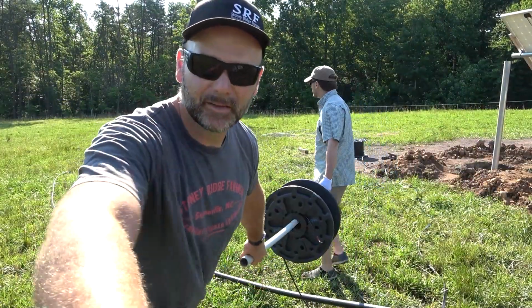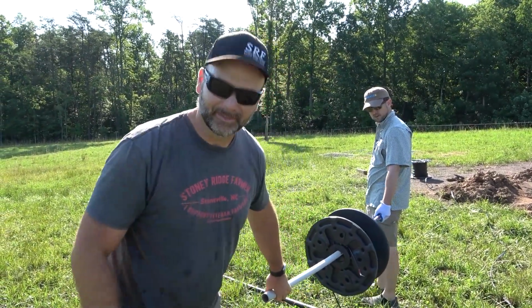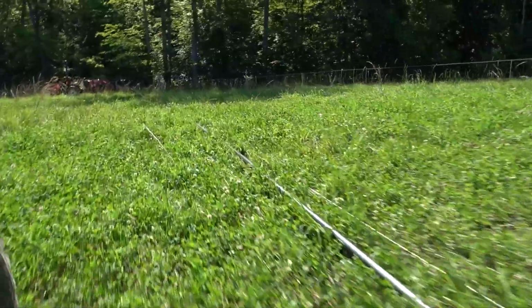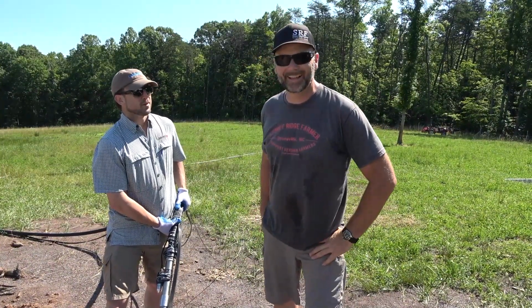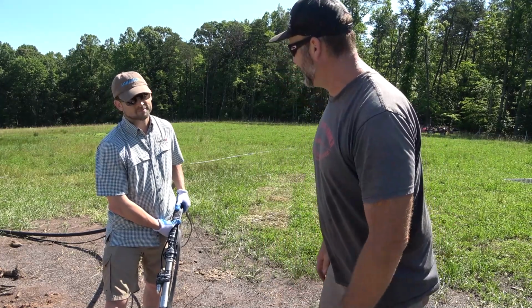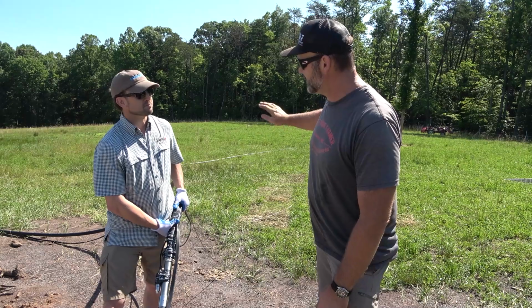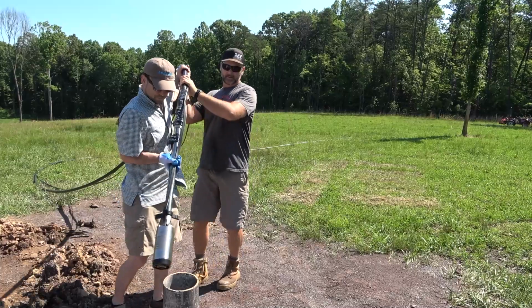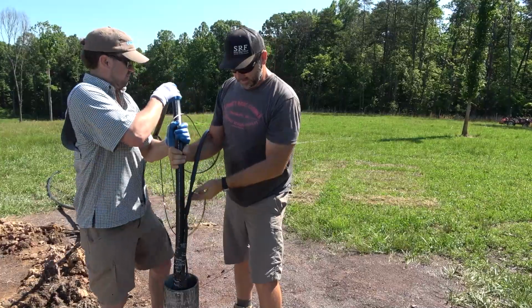It's time for a walkabout. We're gonna run this cable, the sensor cable, all the way out to the end, and then we're gonna run the power cable all the way out to the end. All right, Eric, how big a man are you? I'm counting on you. Yeah, this is gonna be a bear to wrestle, man. And our casing's up a little bit high too, so it's gonna be fun. 200 feet, what did we say, 200, 225, something like that's what we measured off. So we'll start dropping her down in the casing. Bye-bye well pump. See you in 25 years.